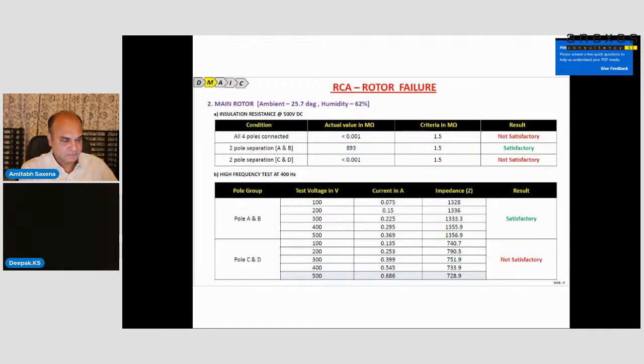So what we did is we separated the poles into A, B and C, D. There are 4 poles. We did the insulation resistance with the A and B poles. It was okay. Then we did the other 2 poles, C and D. The indication is not okay because it doesn't meet the criteria. Afterwards, we did the high frequency test at 400 hertz, grouping the 2 poles. Poles A and B are okay, and poles C and D are not okay.